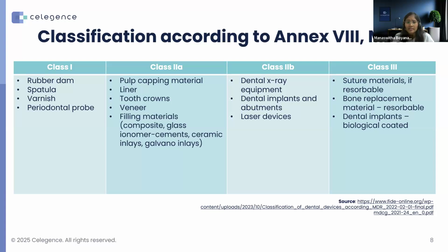So depending upon the risk class of a device, the conformity assessment required submission of clinical evaluation reports, post-market clinical follow-up plans, and in addition, for implants and class 3 devices, an implant card or a summary of safety and clinical performance shall be provided by the manufacturers. It means more scrutiny, more data, and more accountability of how these devices perform clinically.